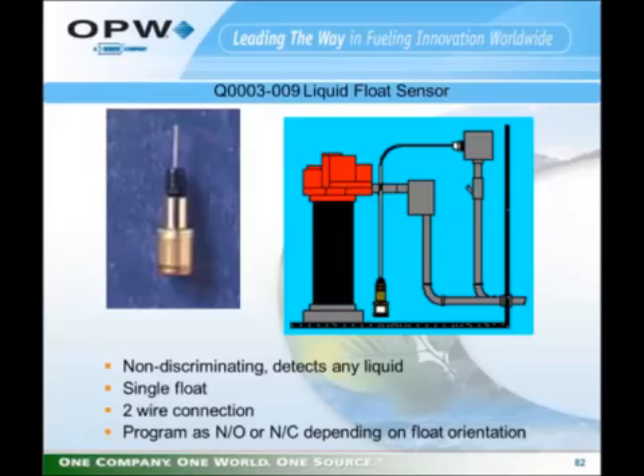Should you wish to change the state on the sensor, there's a clip that attaches the bottom cover of the sensor to the body. You remove that clip, the bottom cover comes off. You can then remove the float, turn the float over, reinstall the float, put the cap back on and the clip back on, and you've changed the operating state from normally closed to normally open.